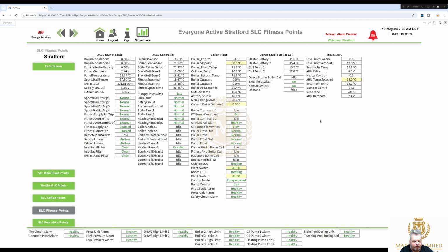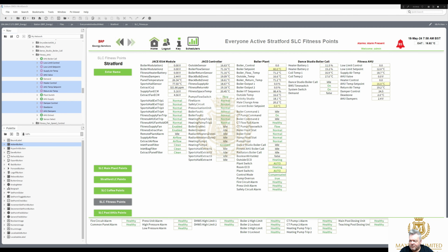They had little touch screens on the panel, hence that's why we're moving them across to a main server. Another good reason for moving across is the histories will be unlimited. So it's not like a 500 point or a 5,000 point and then roll over. It's unlimited histories. So even if it's been in there 5, 6, 7 years, there's 7 years of history. You can't do that on just a touch screen to a controller, and you can't really access it anywhere, only when you're on site in front of the panel on the touch screen.